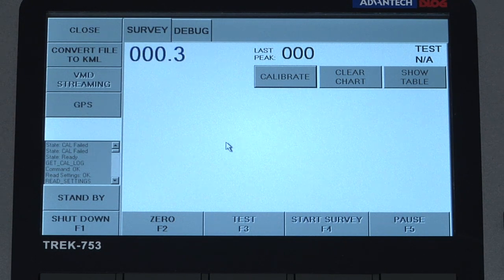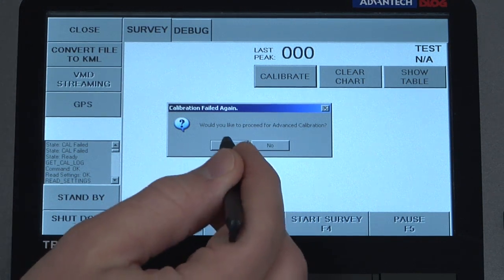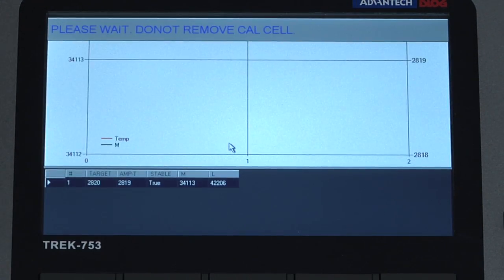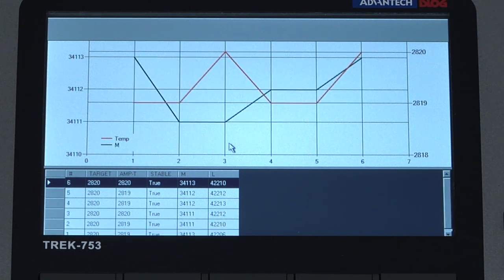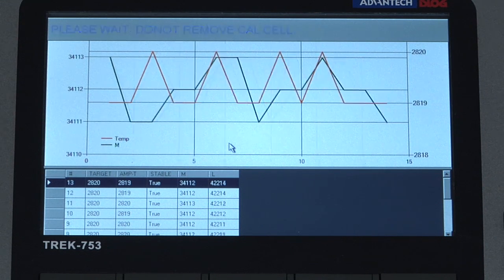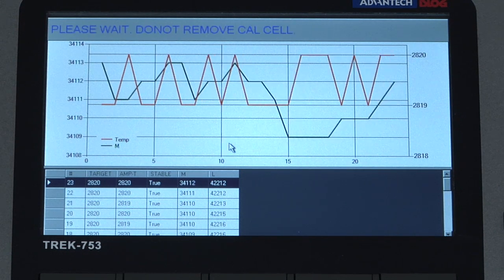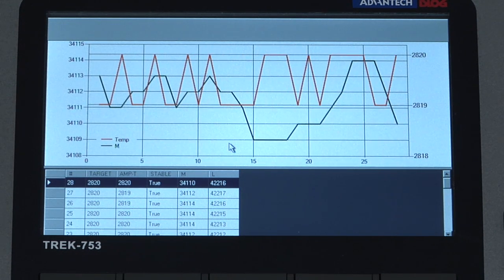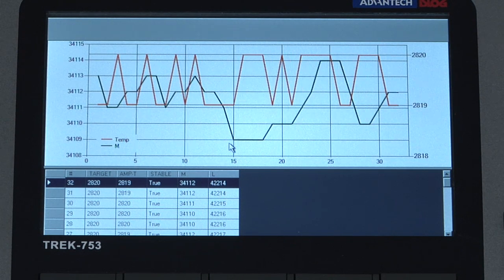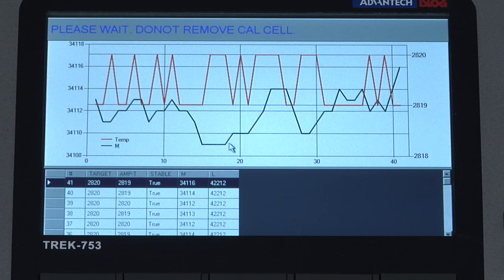The calibration will re-attempt and we will then be prompted to proceed to the advanced calibration. We can hit yes and the screen will proceed to the advanced calibration, showing the same basic debug information for the temperature of the instrument and the light and modulator values. This process will take approximately five to ten minutes to complete and then the screen will return to the standard working display.